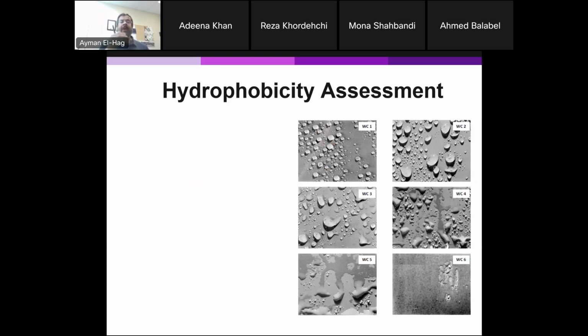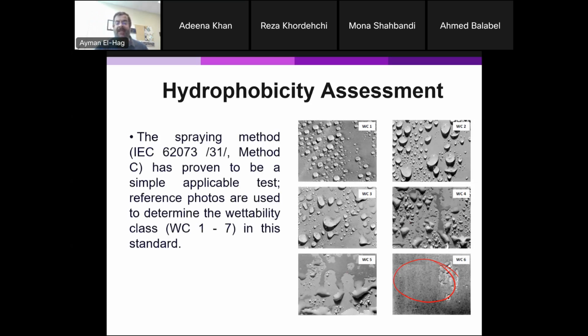But as the insulator ages with time, this property is gradually lost. And you can see here, until we reach here, we have almost complete wetting. And that's an indication that the insulator has basically lost that important hydrophobicity property. So how do we do the test, basically, how can we classify? Now, this was a technique invented by the Swedish Transmission Research Institute, STRI. They came up with this technique, but now the IEC standard has adopted it and made it a guide. So basically, you go to the site, you spray water on the insulator. The sprayer has a certain specification, the distance has a certain specification, and then you take an image.